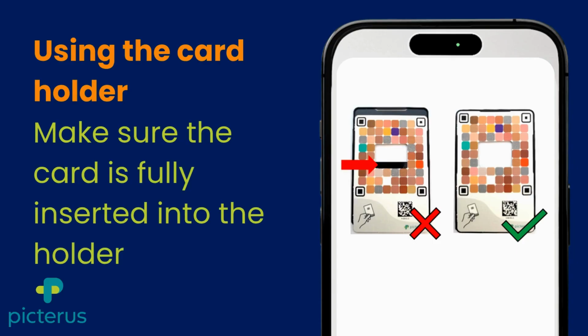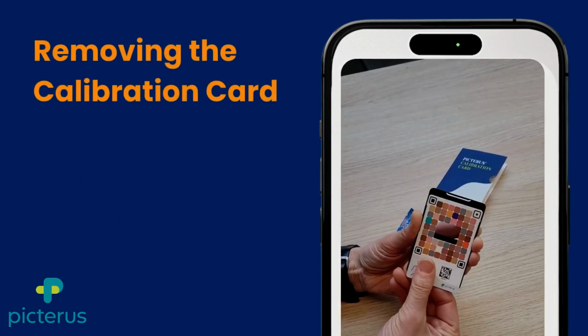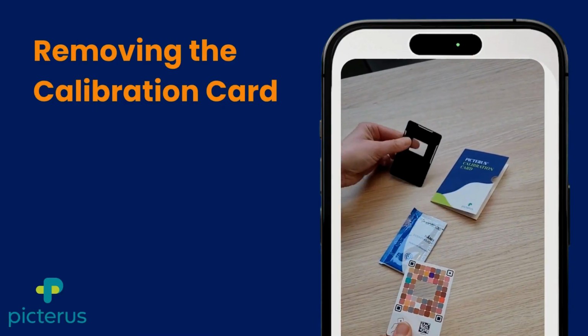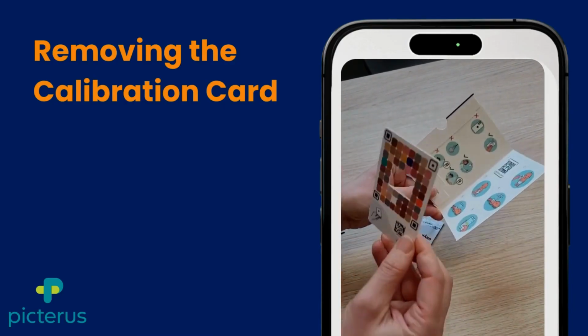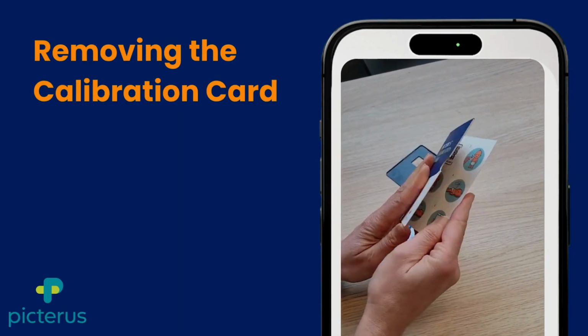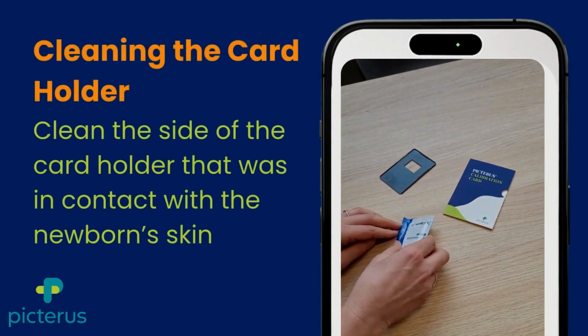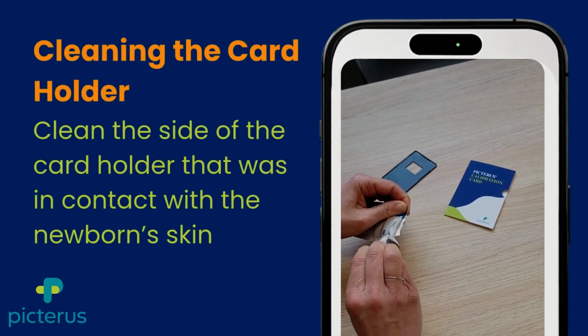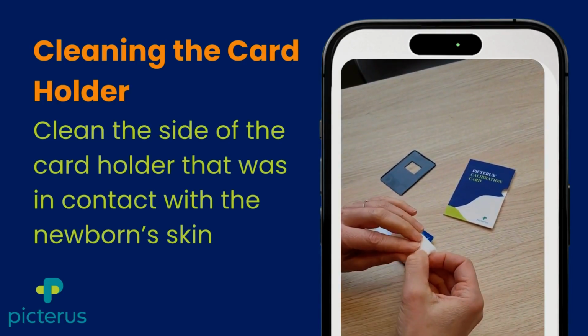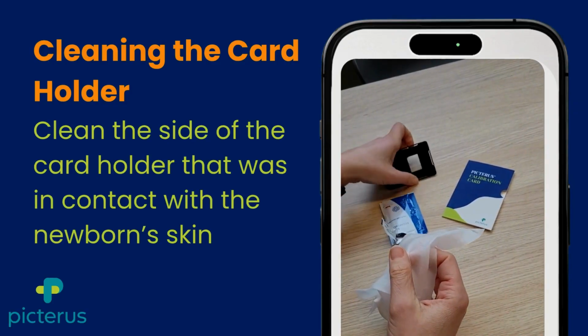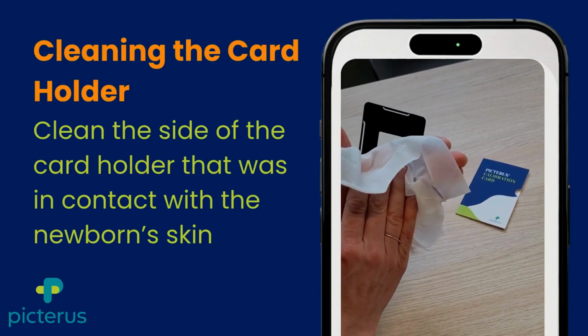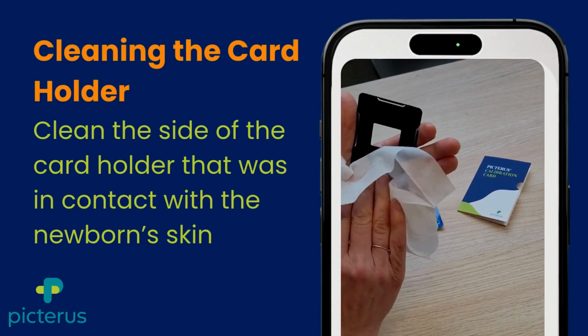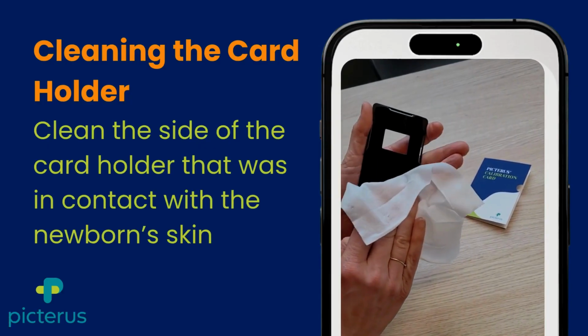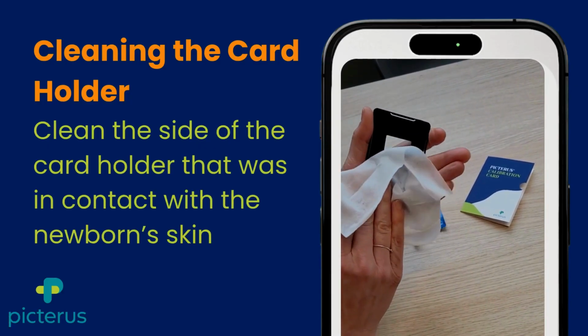Once you are sure the card is fully inserted, you can perform a Picterus scan as usual, according to the instructions for use. After completing a scan, slide the calibration card out from the holder and store it safely in the packaging. Clean the card holder using an alcohol-based cleaning solution or wipe. We recommend 70 to 90% isopropyl alcohol, or 60 to 80% ethanol. Thoroughly clean the backside of the card holder that has been in contact with the newborn's skin. Allow the card holder to completely dry before inserting the calibration card to make a new scan.